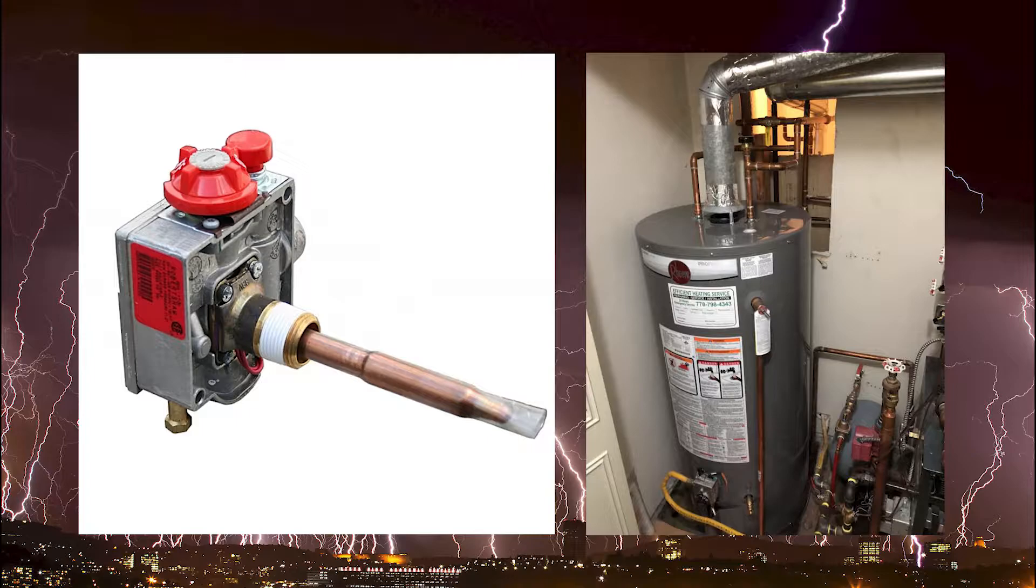What you can't see is a little metal rod on the inside of that tube called Invar. Invar has a property where it doesn't expand and contract a lot when heated and cooled, considerably less than a copper tube. So that's actually going to open and close the gas valve just by mechanical action.